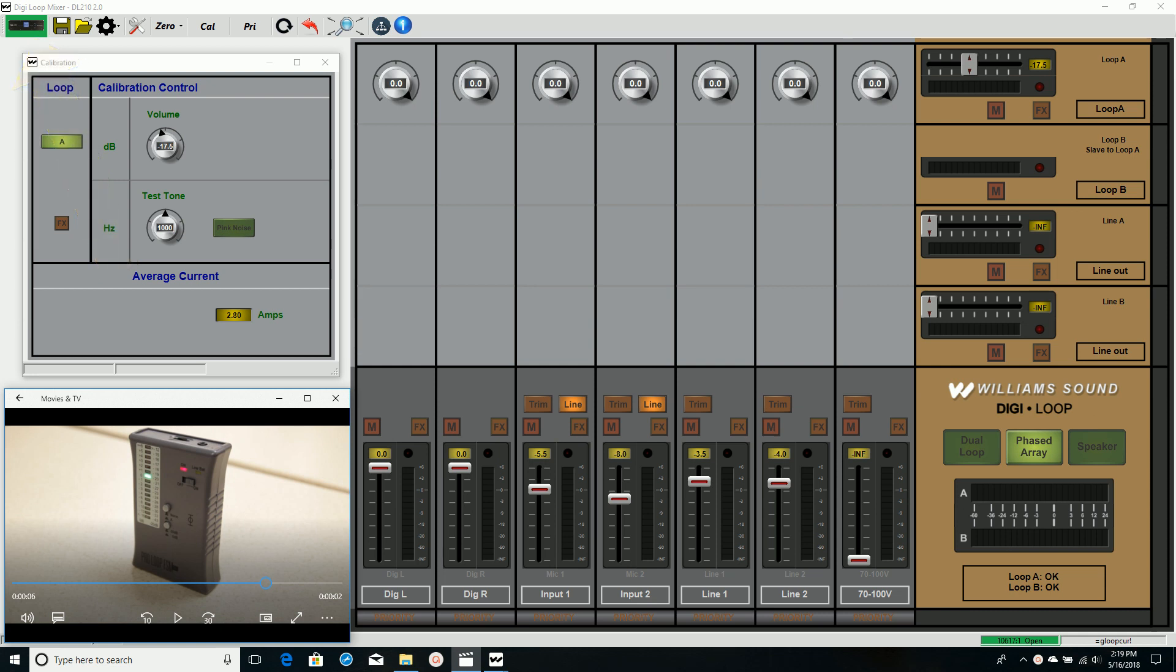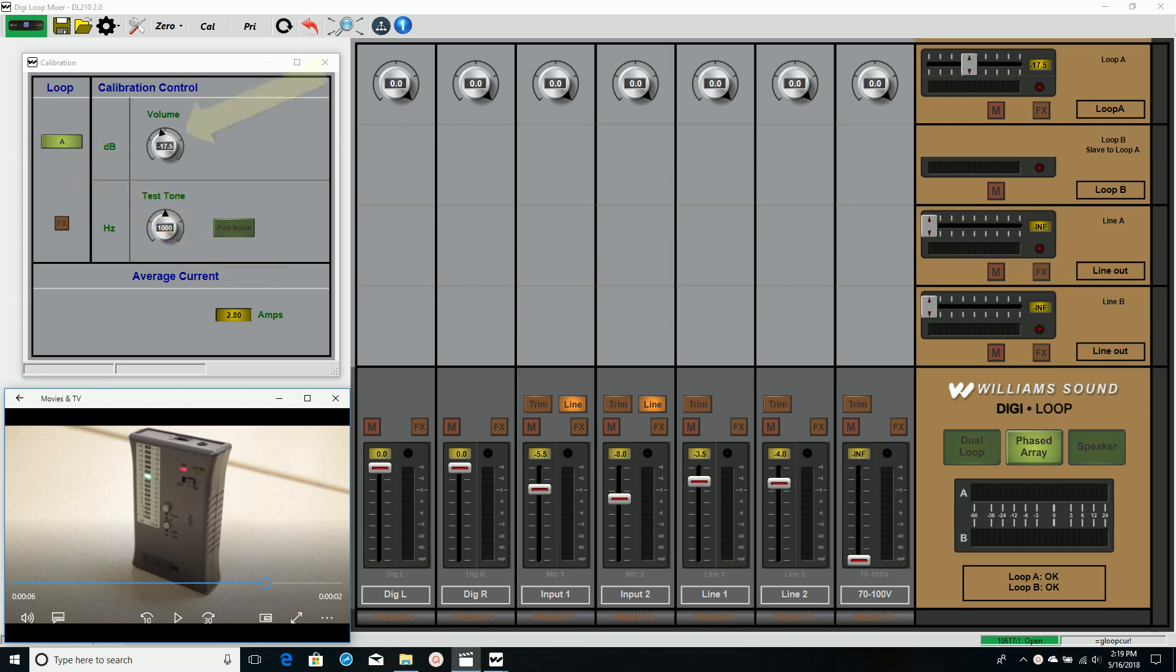A phased array has two loop wire arrays overlaid at an offset. This calibration window will bring up loop A which I will adjust until the field strength meter shows 0 dB.